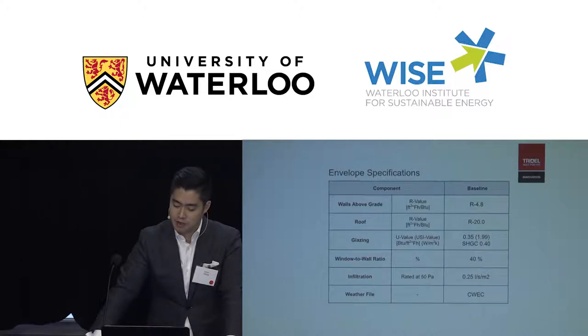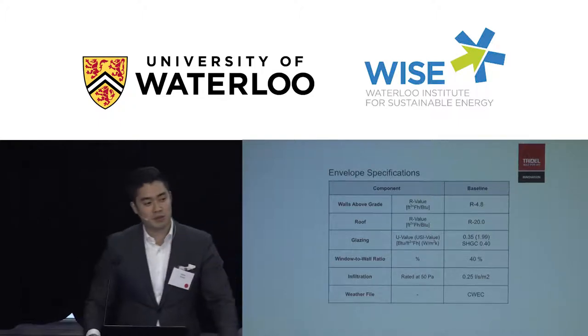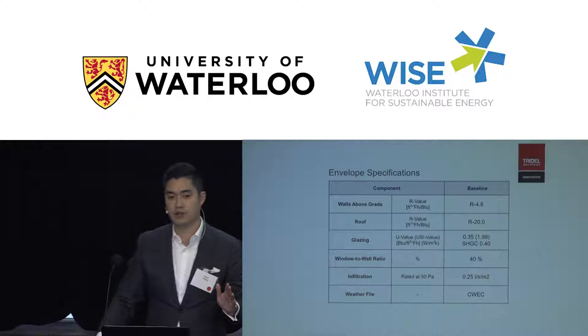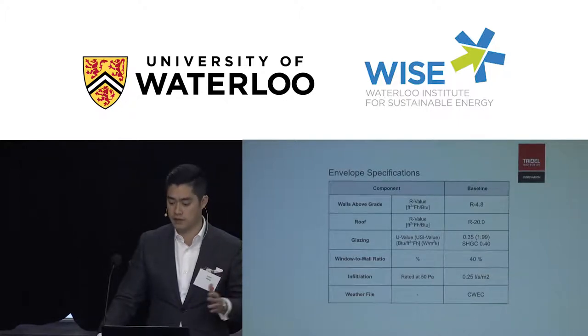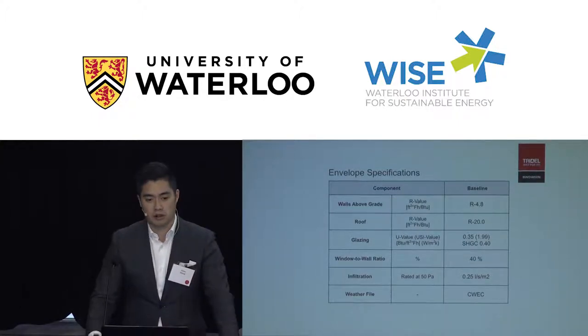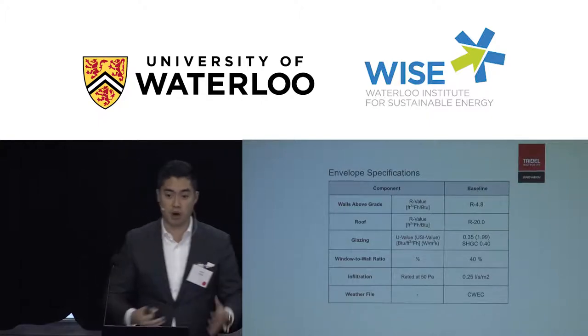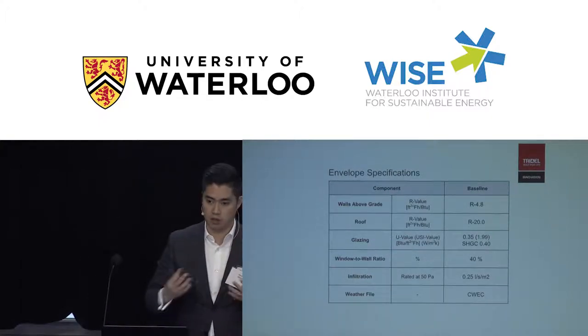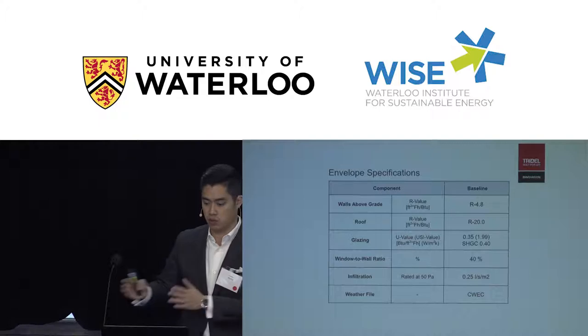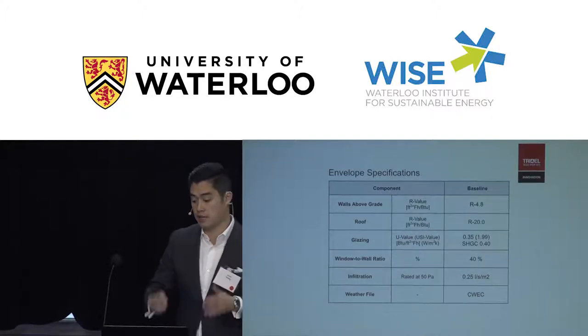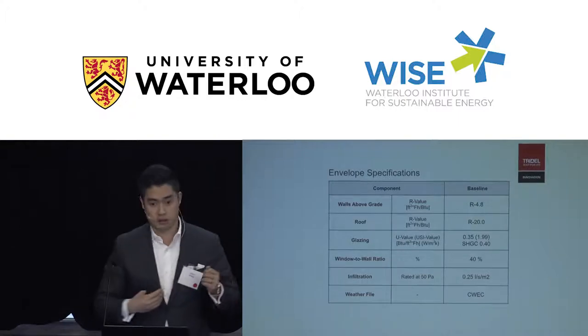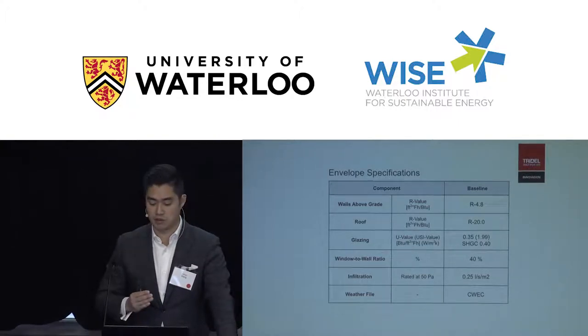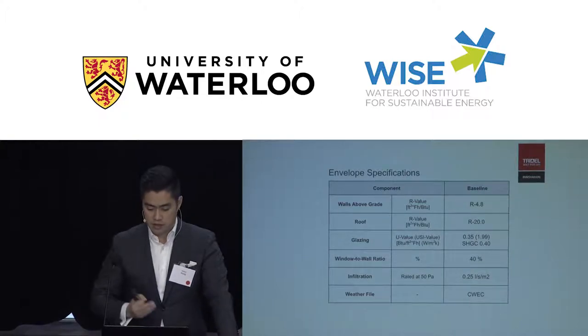The first number that's probably going to hit you between the eyes is that the wall above grade R value is very low. It's important to note that this is the effective R value, and there's a big difference between the nominal R value and the effective R value. The nominal R value of our buildings is close to R30. But with the latest round of energy code changes and the way we model our buildings, we now have to take into account all the thermal loss—the thermal transmittance from different materials like precast, spandrel, window wall, and the balcony slabs themselves. Because of that, the effective R value has dropped tremendously down to about R4.8, and that's hitting our energy model really hard right now. That's part of the changes we're going through.